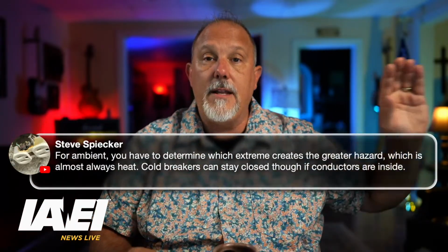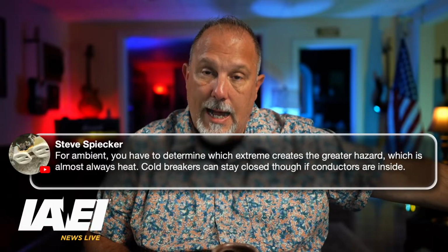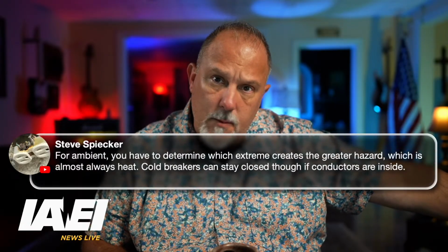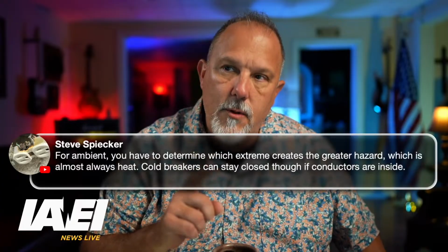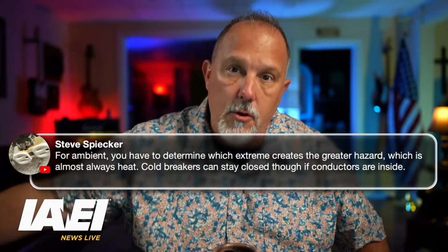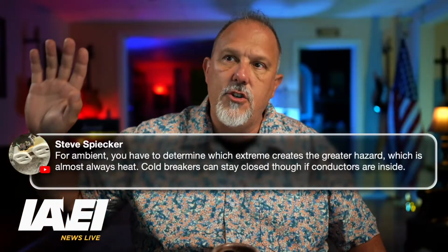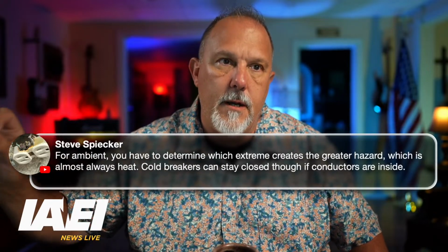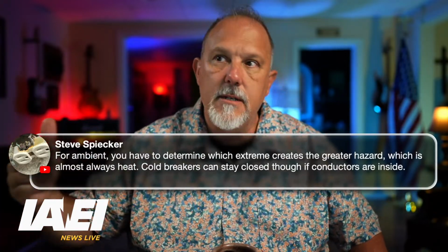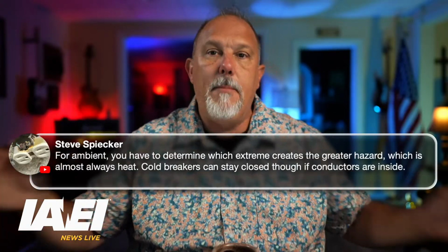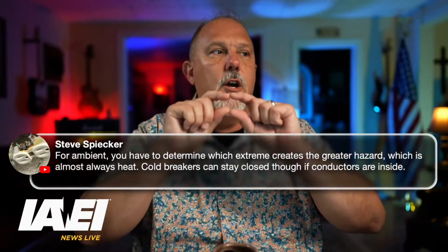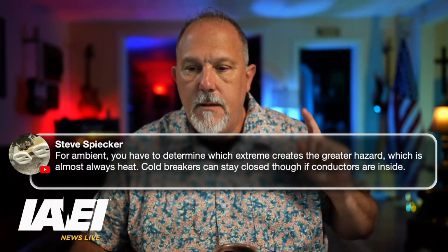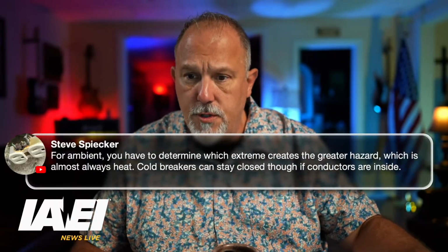I agree with you that with temperature, I will have limitations for the proper application of my overcurrent protective devices, whether they're fuses or breakers. I will also have limitations of application of the loads, which may be HVAC, it could be fans, could be a motor. I have to consider operating that equipment, appliances, in the elevated ambient as well. But what we're talking about right now is protection of a conductor, period. All right? But very good point, Steve.